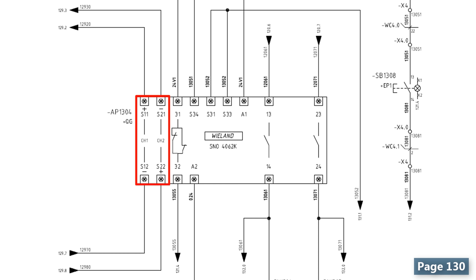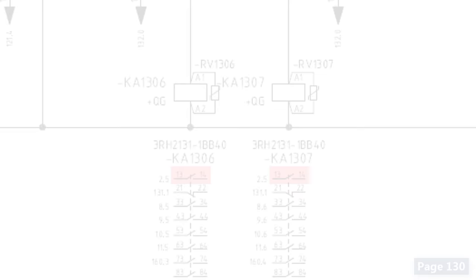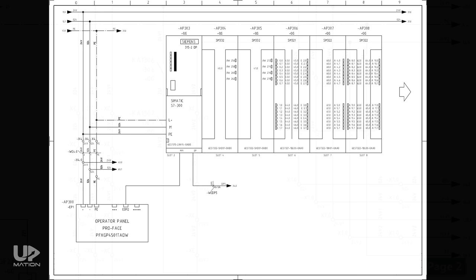And if the area is evacuated, then these channels will be activated and as a result these NO contacts become closed. Thus, the voltage will be transferred to the A1 connection of the relay's coils and finally the coils will be energized. Therefore, our 13-14 NO contacts of the relays become closed. In this way, our 24V power will be transferred to page 12, column 0.